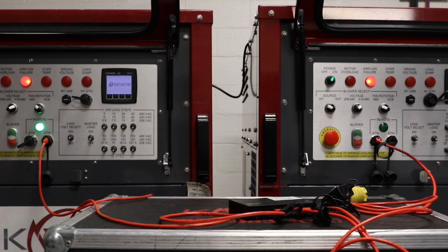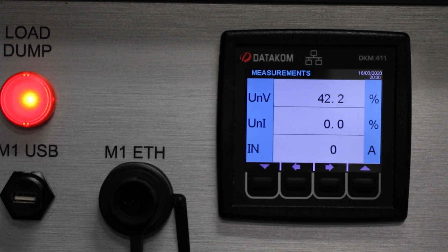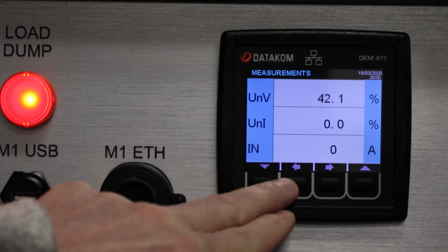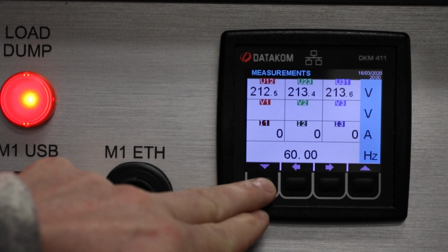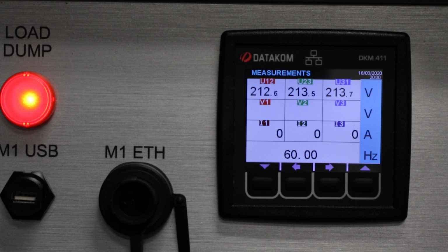Second, why would you want to set up multiple groups of load banks? The main reason is if you have multiple outputs on a system that you're tying the load banks into. For instance, you could have multiple breakers fed from the same generator system, but the breakers are set to trip at different amperages. You can put the load banks into groups based on these ratings to ensure that you don't trip anything during testing and that everything is still coordinated as a single load bank system.